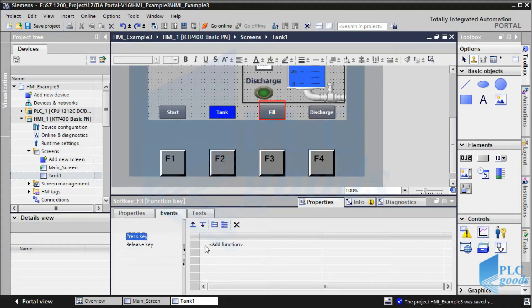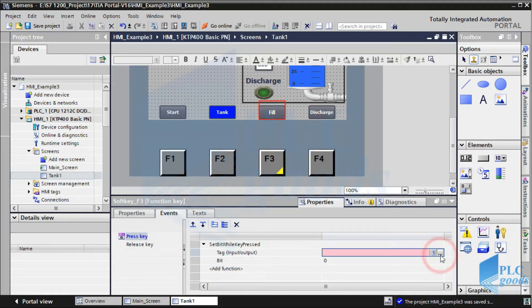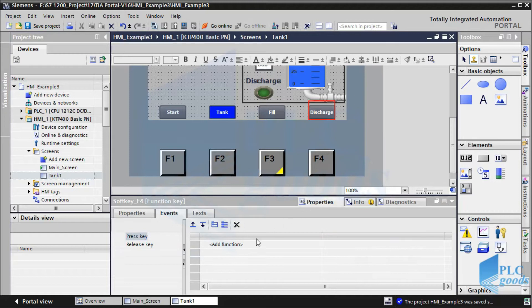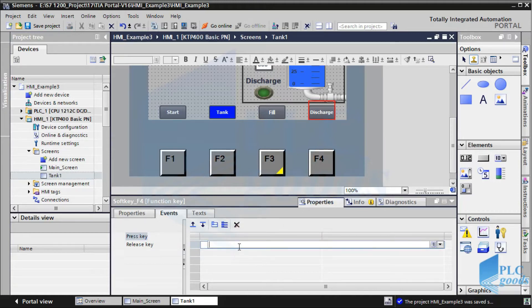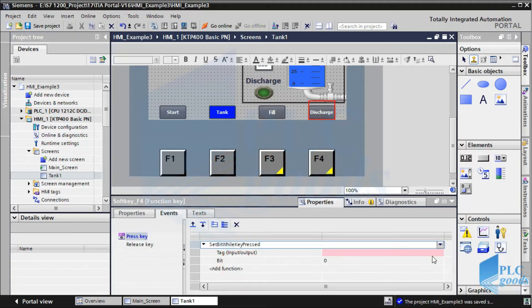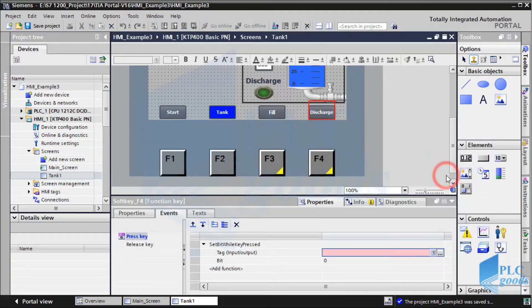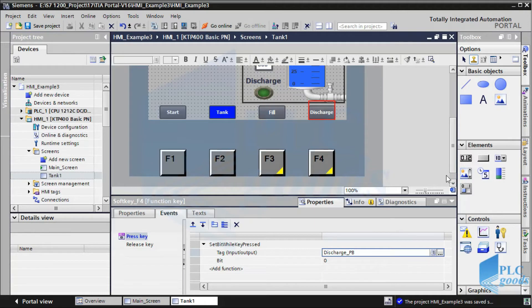This is very simple — in its event tab, select this function and connect it to the fill tag of the PLC program. Also let's use the F4 key for tank discharging. As you see, when a function is defined, a yellow triangle will be shown on the related function key.